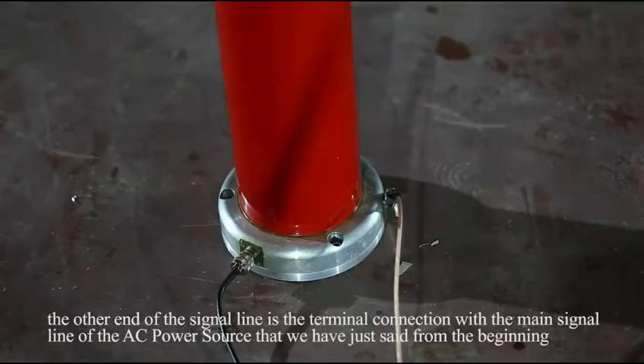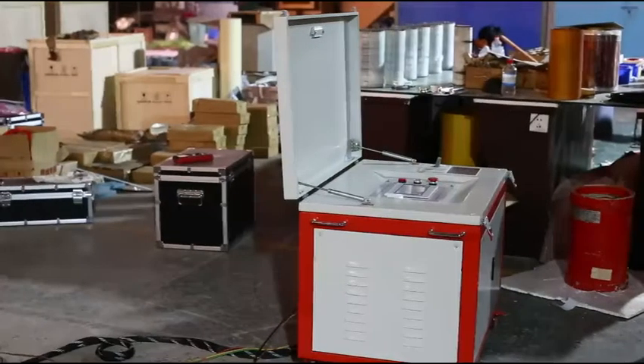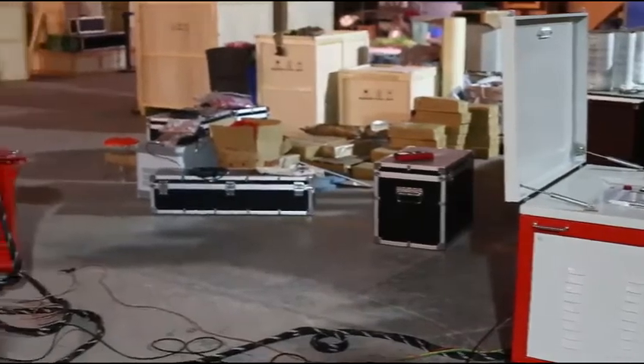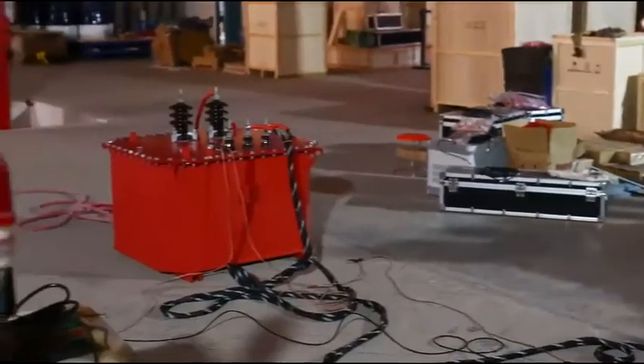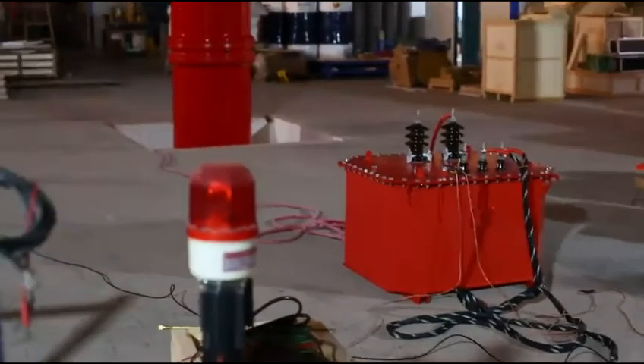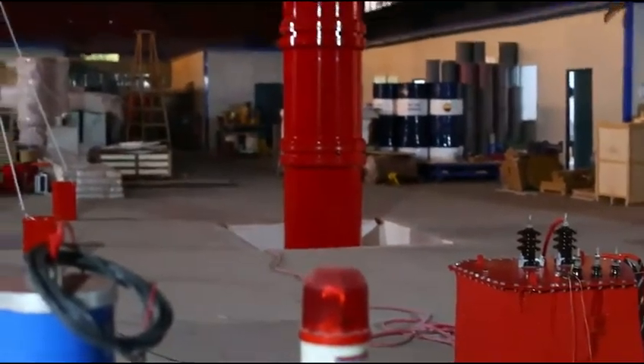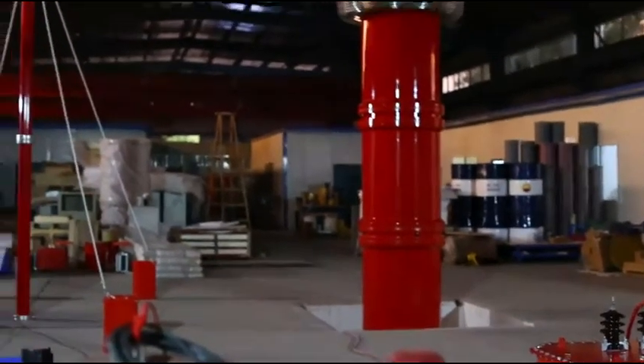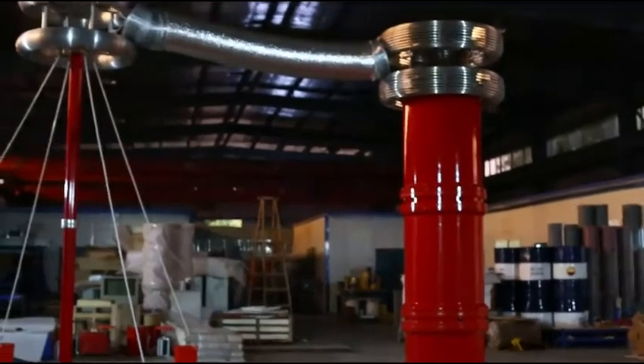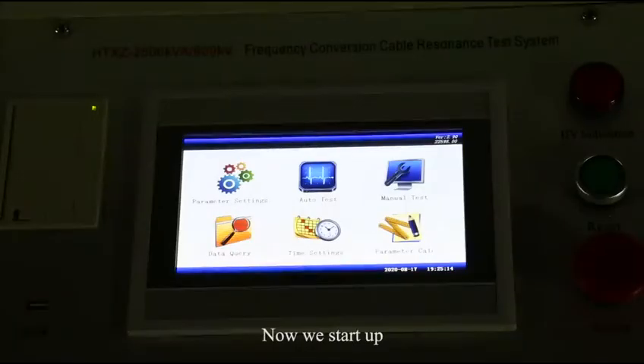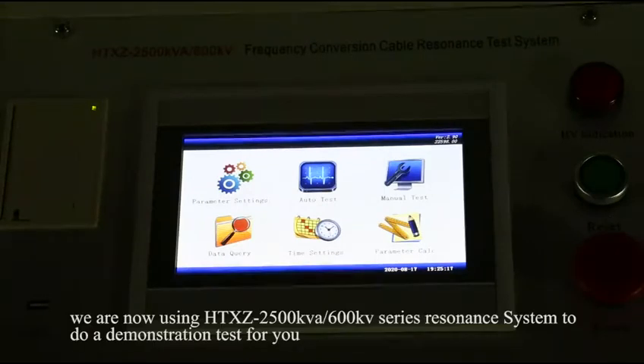The other end of the signal line is the terminal connection with the main signal line of the AC power source that we have just set from the beginning. Now we start up. We are now using the HTXZ 2500 kVA and 600 kV series resonance system to do a demonstration test for you.